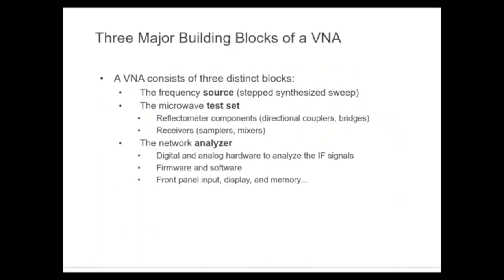Now we'll look at the hardware behind the VNA — what's inside and how these measurements are made. The VNA has a fully synthesized signal generator as the source. It's a stimulus-response system. We then have a test set with components that allow us to separate transmission and reflection signals for our receivers. And behind all of that is the analyzer itself — the digital and analog hardware, IF sections with A-to-D conversion and amplification, plus firmware, software, front panel display, and memory. These are the building blocks of the VNA.